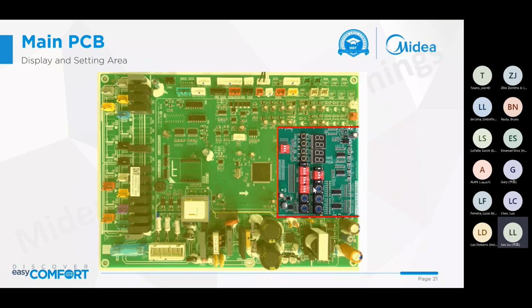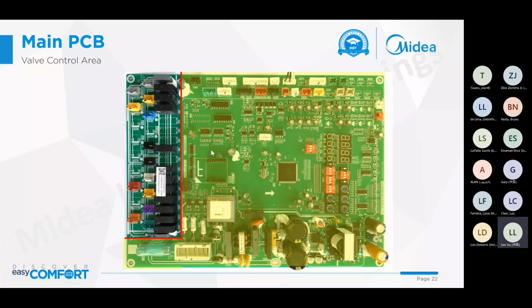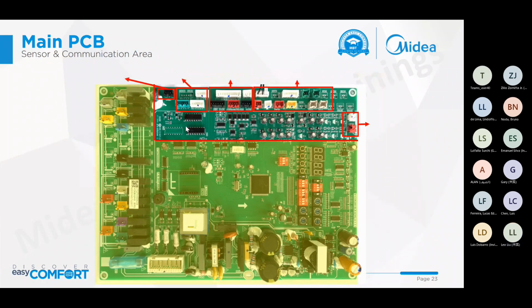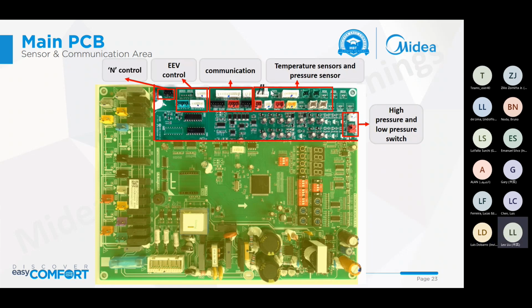Okay, the right side is the display and setting area with the menu button, LED display, and the DIP switch. The left side is the strong power area, with relays for the four-way valve and solenoid valves. On the upper area, this is for the sensors and communication. There are a lot of sensors, like temperature sensors and pressure sensors, and communication ports for the indoor units and centralized controller, and the EXV control, high pressure and low pressure switch. This is the port.